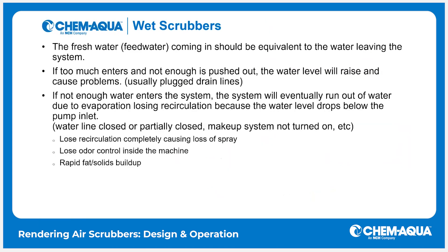Fresh water coming into the machine should generally be about equivalent to the water leaving the system. If we have more going in than leaving, we'll fill the machine full of water over time, which can plug the airflow through the scrubber and shut down the process. If not enough water goes in, we will lose some to evaporation and the air scrubber could run completely out of water, rendering it effectively useless at capturing odors, fats, and solids.